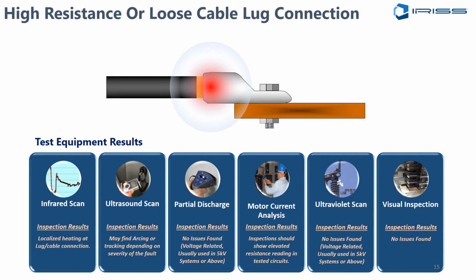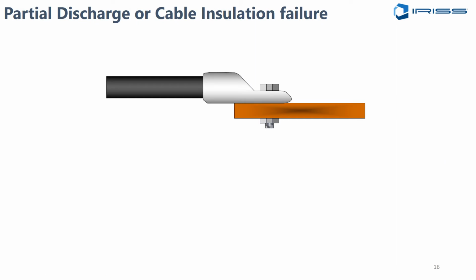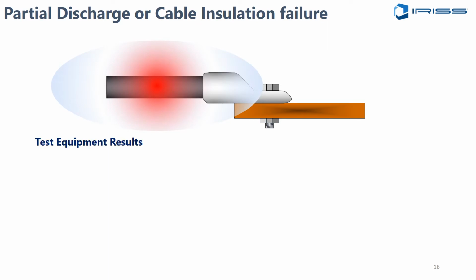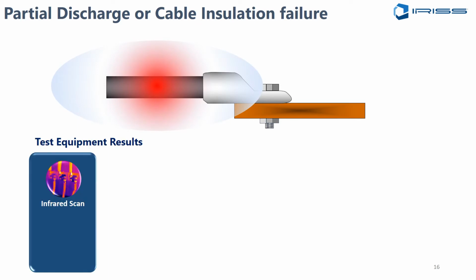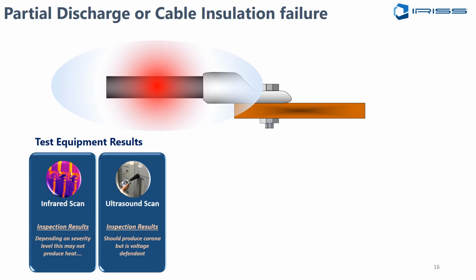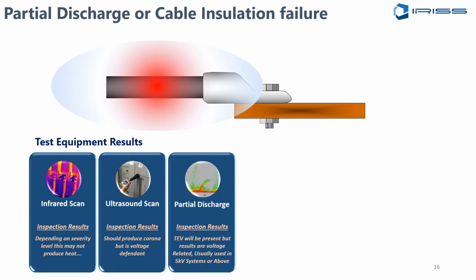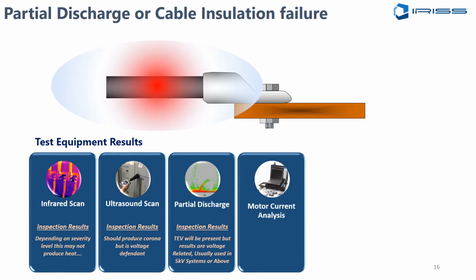Now the final failure mode we're going to look at is partial discharge or cable insulation failure. Typically partial discharge doesn't produce heat. Only in very, very extreme cases have I seen reports of heat being produced. But then we're getting into the arcing and tracking side of life. So typically in infrared, no heat. However, with ultrasound above 5 kV, we're going to hear corona. Partial discharge scanning using PD or UHF scanning, we're going to see that again. Don't forget, PD is typically 5 kV or above.